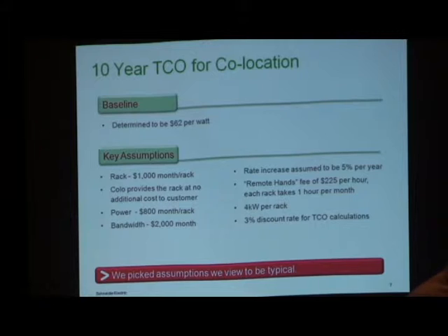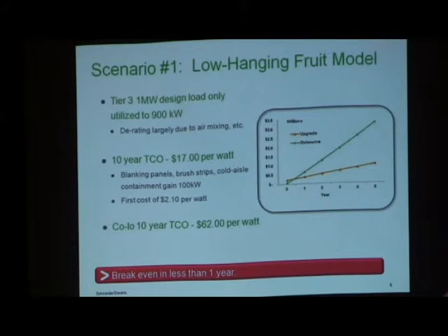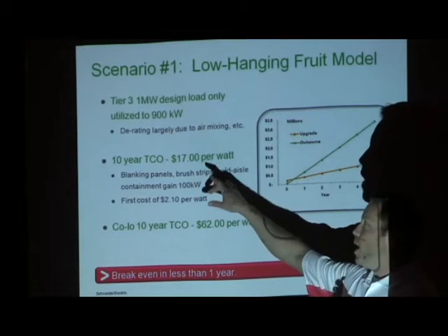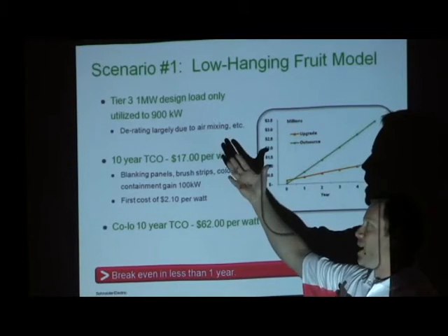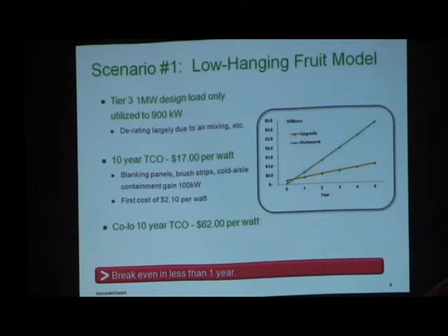This is just a baseline for where we came up with some calculations that I'm going to show you here. Scenario 1, the low-hanging fruit model. What's our break-even point for doing those air mixing fixes that I was talking about? Keep in mind, this is showing a 1 megawatt data center, utilizing 900 kilowatts of load. I know there's not a lot of 1 megawatt data centers here in Utah. We've got a couple, but not most everyday data centers. But this also plays out on a smaller scale, we've found, as well.